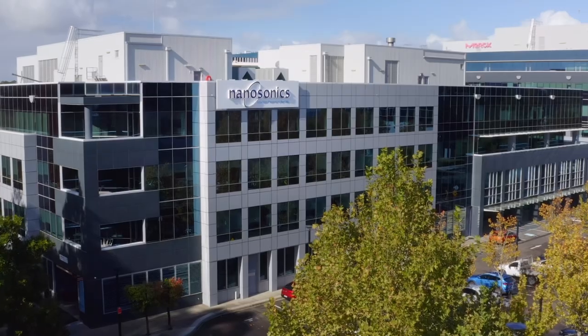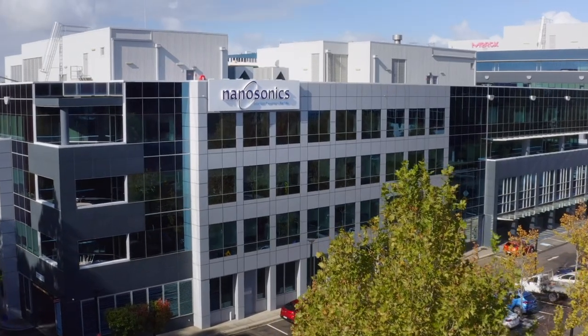So all those manual considerations are taken away with Trophon. It actually controls all of the critical process parameters. So in our case, it's the concentration of the chemistry, the dosage into the chamber, the temperature. The coverage is taken care of, obviously, with the mist. And then you have that chemical indicator that's a cycle verification. That's telling you the right amount of oxidative chemistry entered the chamber. Sounds like peace of mind. Right. Yeah. Confidence.